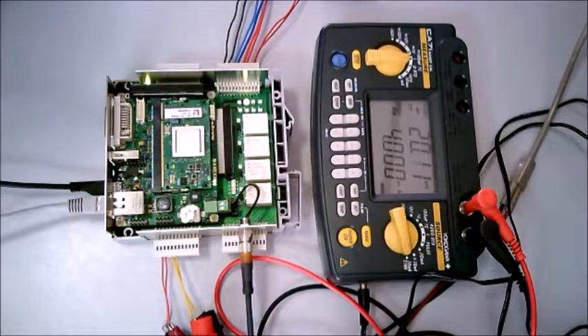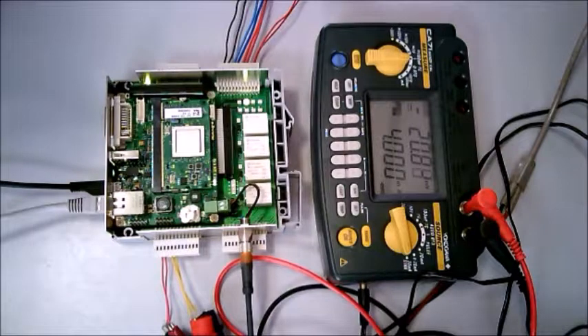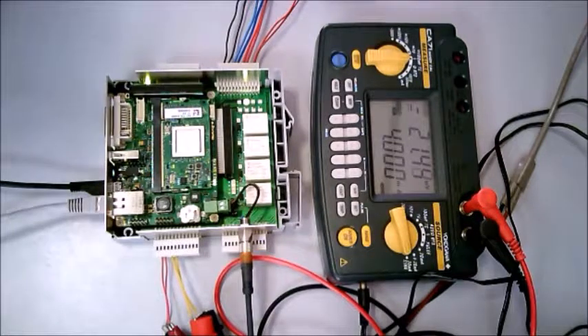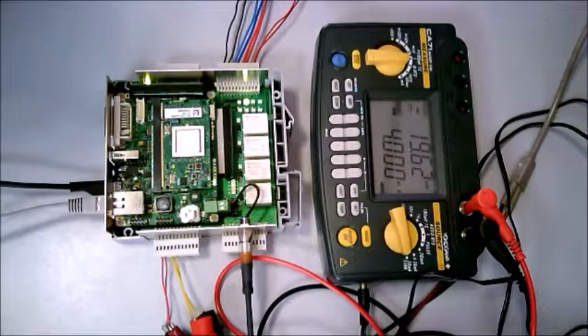We are going to explain the hardware requirements to make a proper connection and calibration of the analog inputs of the TESDA board. As you know, the analog inputs accept the 4 to 20 milliamp input signal format, both in active or passive mode. You can see the correct connection diagram in the user manual of the TESDA board, which is available for downloading from our website.